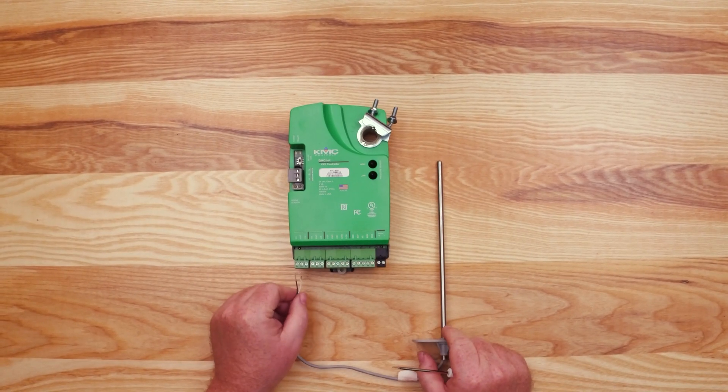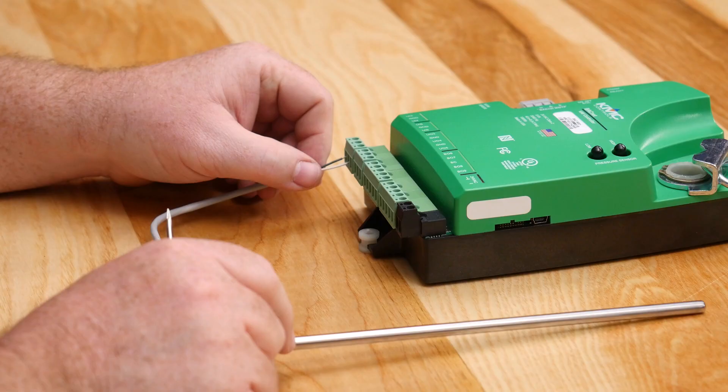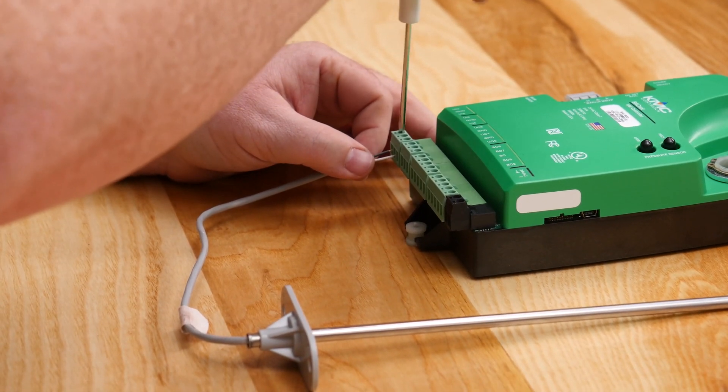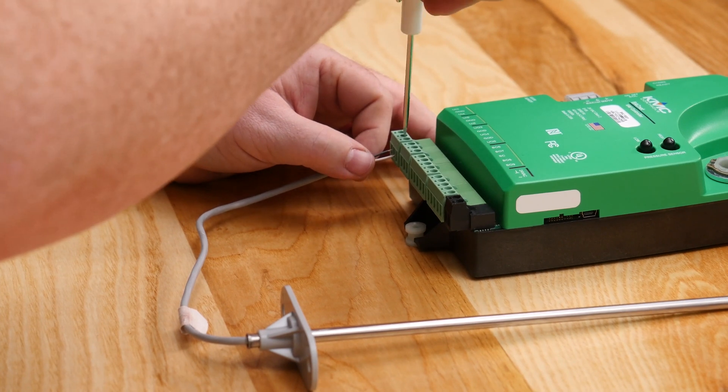When wiring the inputs, always make sure there is no power to the unit. The inputs consist of two wires, a signal wire and a common wire. Working with the first terminal block, insert the signal wire into the UI3 terminal and the common wire into the adjacent GND terminal.